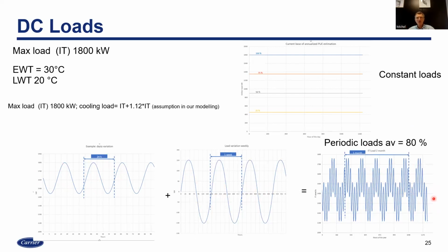You can also receive data from a customer showing their load pattern through the year and their location. We can calculate what their energy consumption should be with and without free cooling. This is what I'm trying to show - for all the locations we looked at, whether I have constant load or variable load, what's the impact of equipping the data center with or without free cooling.